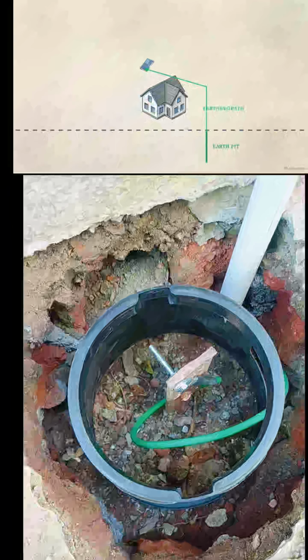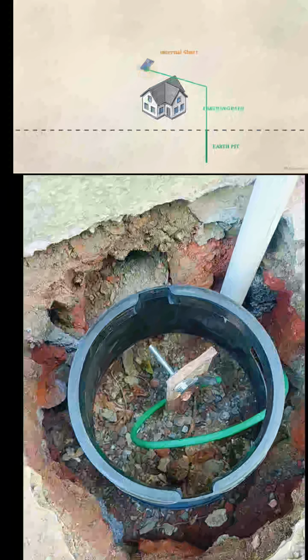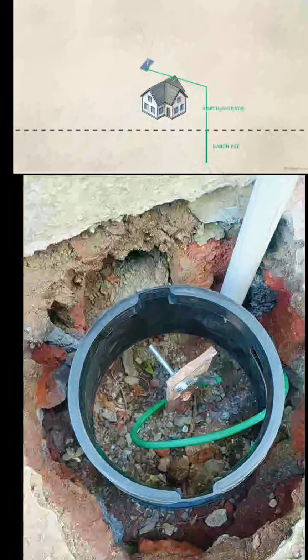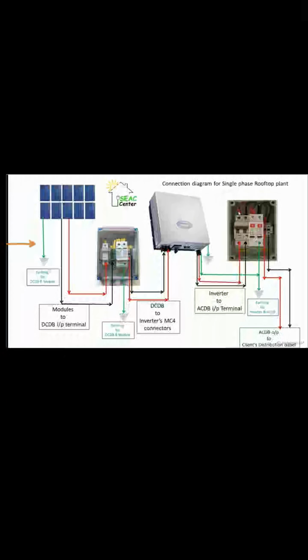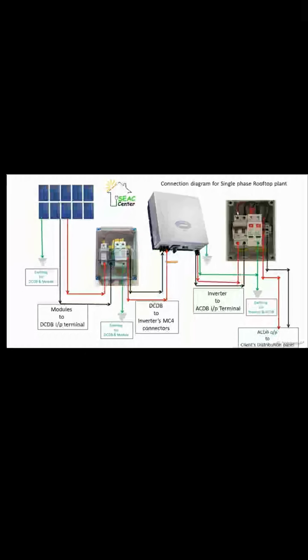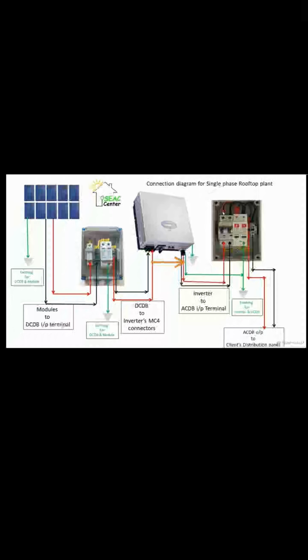The earthing system acts as your critical escape route for stray voltage, whether from an internal short circuit or an external lightning strike. On the schematic, the green arrows on the left mark our first earthing path, connecting the module frames and DCDB to a dedicated earth pit. The right side green arrows show the second path, wiring the inverter and ACDB chassis to a completely separate earth pit. You must never tie these two paths together.